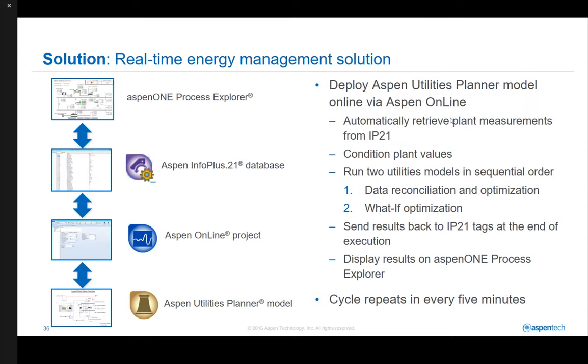Once the offline model is validated, it will be connected with the plant data via Aspen Online. The plant data is automatically retrieved from the IP21 database via Aspen Online. The raw plant values will be conditioned and sent to the models. Two utilities models are executed in sequential order. First, data reconciliation run followed by the main optimization is accomplished in the first model. Then, the what-if scenario model is executed based on the changes in the utilities demand and production entered by the operators. Once the model converges, the results from the model will be updated in user interfaces developed in Aspen One Process Explorer. The entire cycle repeats every five minutes.